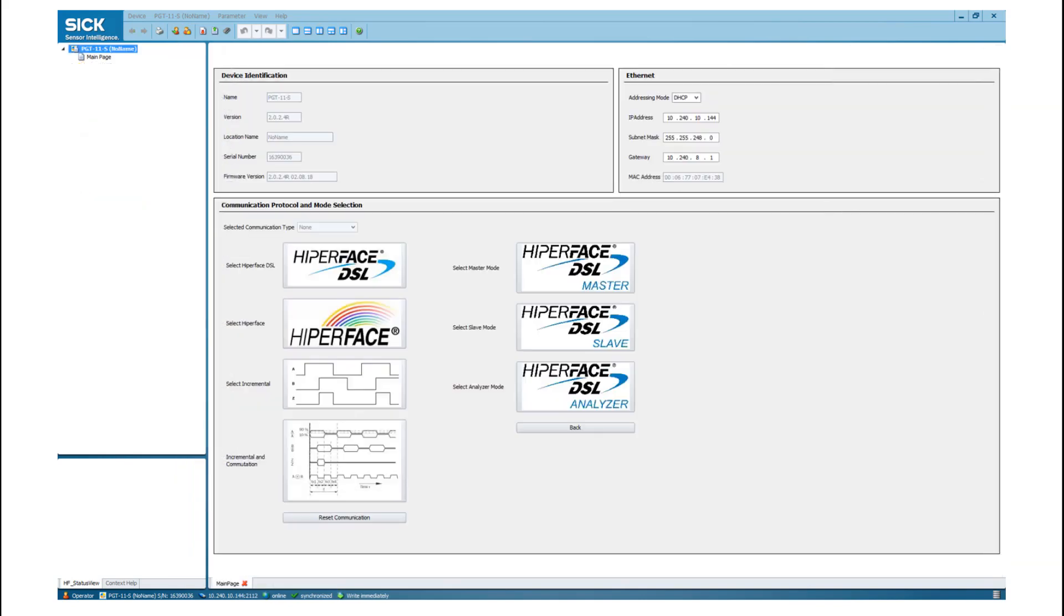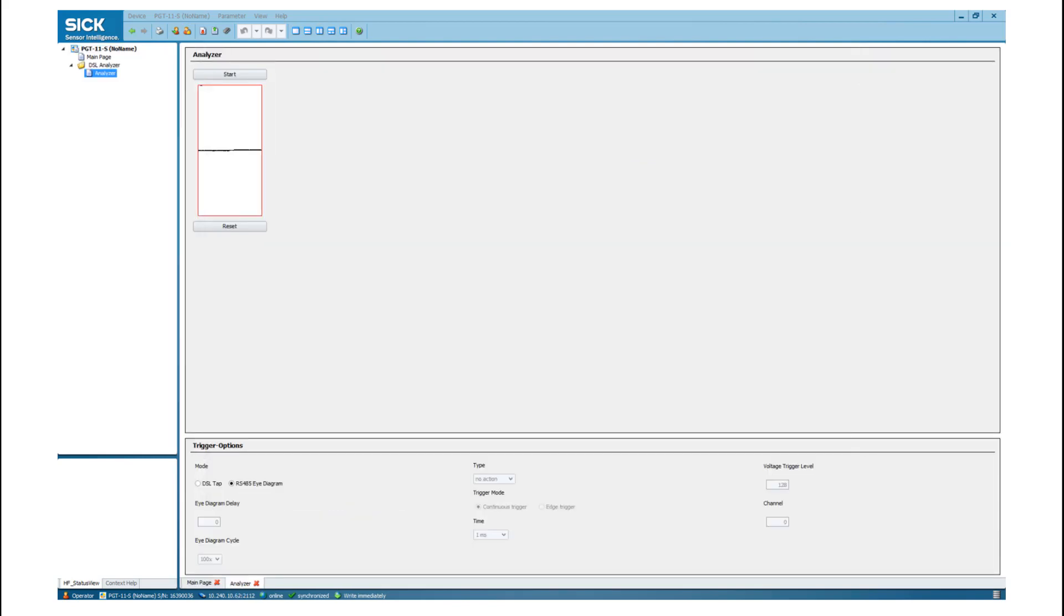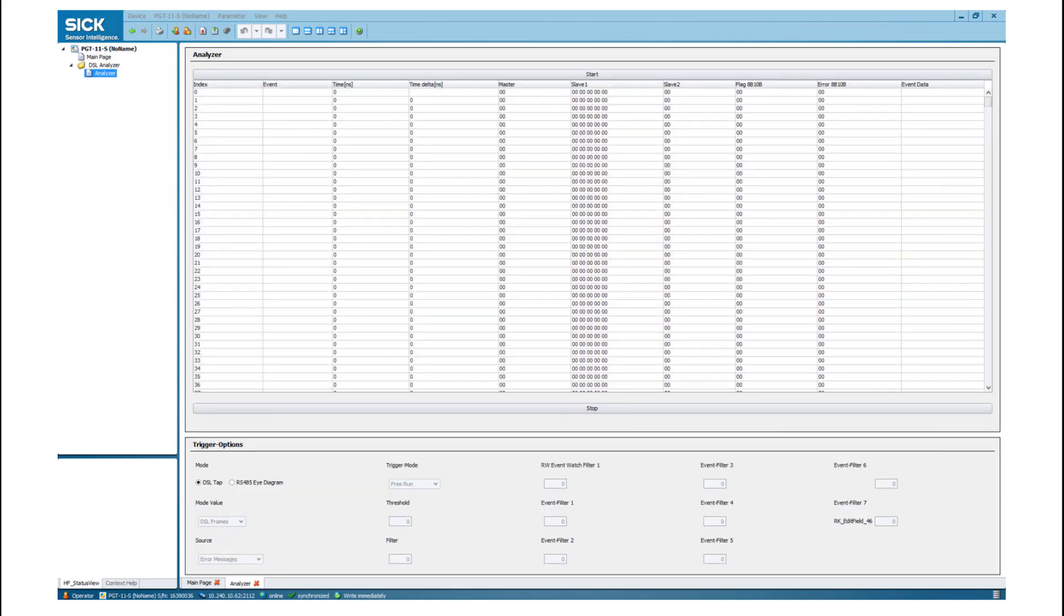If you want to change to the Hyperface DSL analyzer mode, please go back to the main page. Here you can select the analyzer mode. In this mode, the PGT11S must be connected between a servo drive and a servo motor or a Hyperface DSL encoder. In the analyzer mode, only one tab is available. Here you can see the eye diagram of the signals on the line. It is a possibility that the scale of the diagram is poor. If you tick the box DSL tab, the upper part of the screen changes. Here you can start to record the communication on the line. But this is only suitable for rough analysis as the PGT11 is not able to catch every frame of the Hyperface DSL communication.